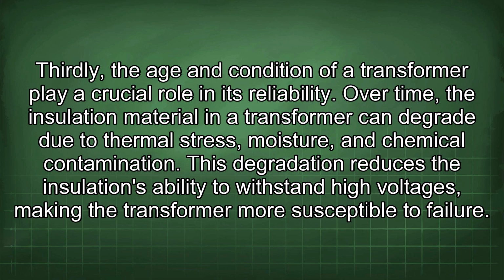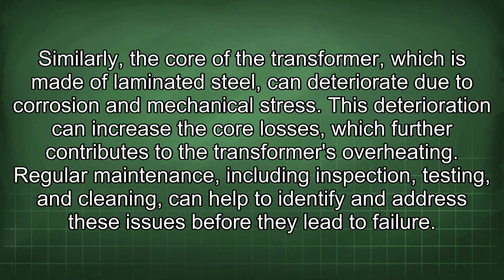Over time, the insulation material in a transformer can degrade due to thermal stress, moisture, and chemical contamination. This degradation reduces the insulation's ability to withstand high voltages, making the transformer more susceptible to failure. Similarly, the core of the transformer, which is made of laminated steel, can deteriorate due to corrosion and mechanical stress. This deterioration can increase the core losses, which further contributes to the transformer's overheating. Regular maintenance, including inspection, testing, and cleaning, can help to identify and address these issues before they lead to failure.